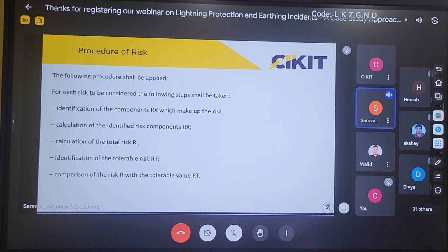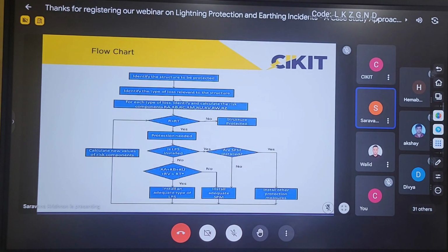So this is the flowchart provided by the standard. Here you can observe that we have to repeat the cycle till the value of R becomes less than RT. First I will be performing the calculation without any protection measures. If the value is greater than RT, then I am going for level 4 protection. In the probability of damage, I have shown how the values change if I change the level of protection. I am just going to the slide.